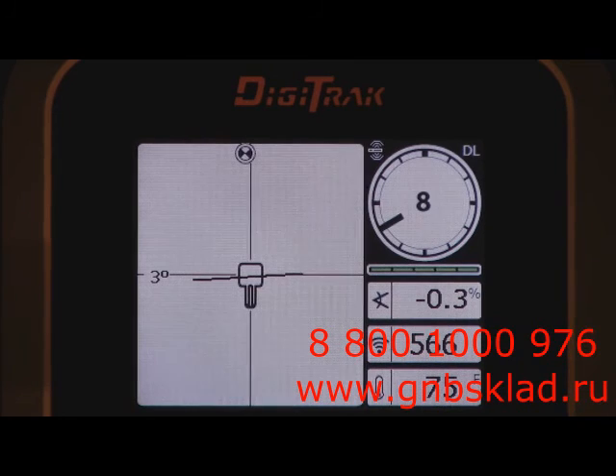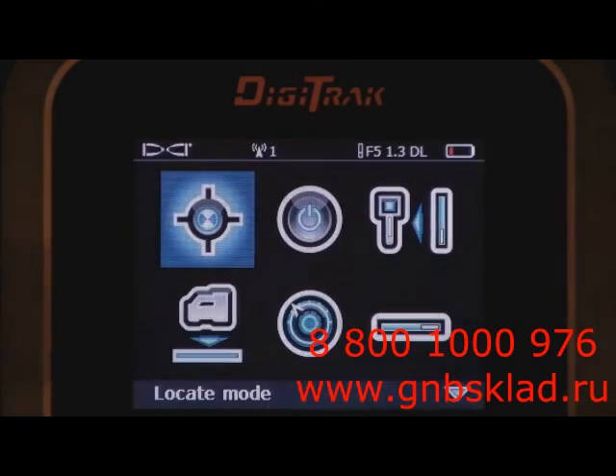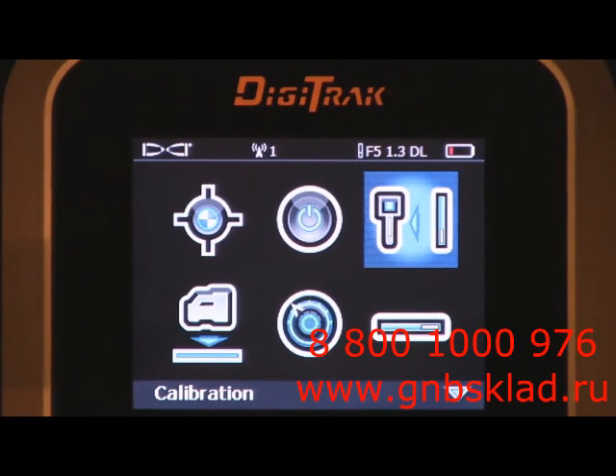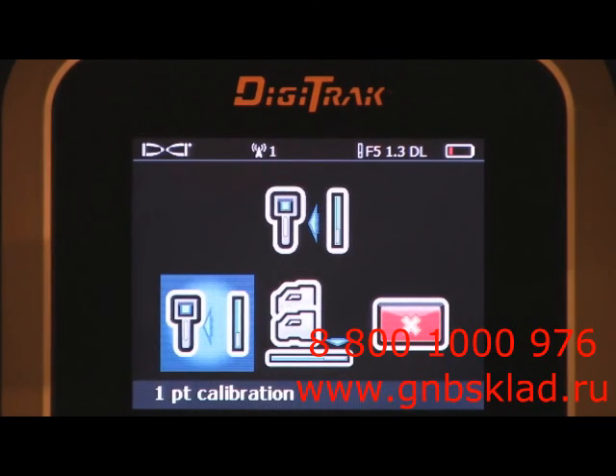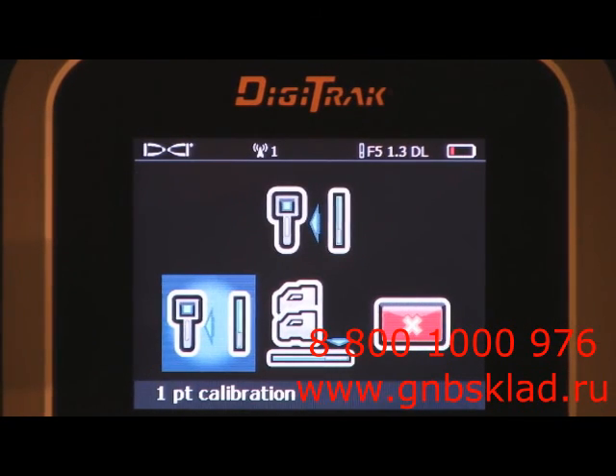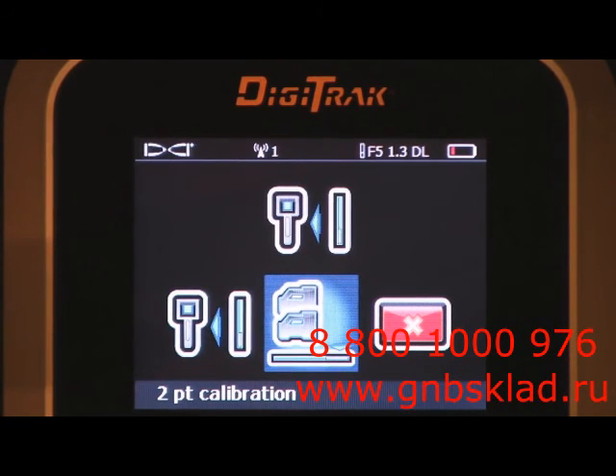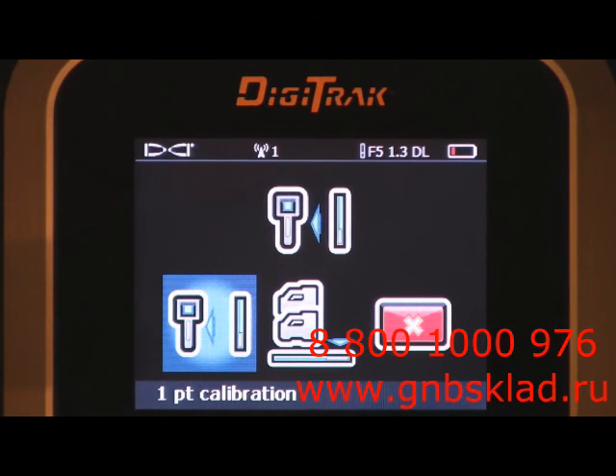Okay, so let's go ahead and back out of this. We verify the transmitter is working. We'll slide it over back to the calibration menu. Here we go. We'll click it. Now we have two calibration choices, a 1-point and a 2-point. The 2-point calibration is reserved for when the transmitter's underground. This video, we are not going to discuss the 2-point. We're going to discuss the 1-point calibration.